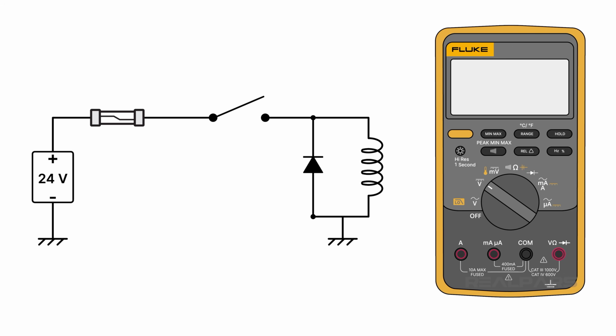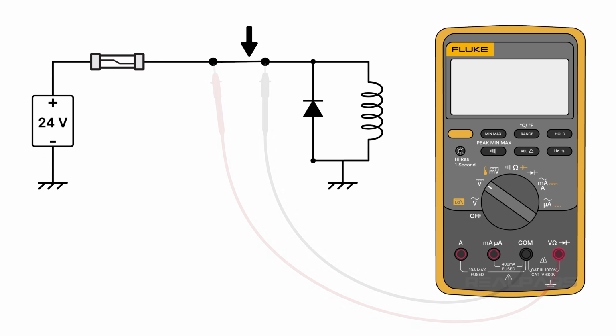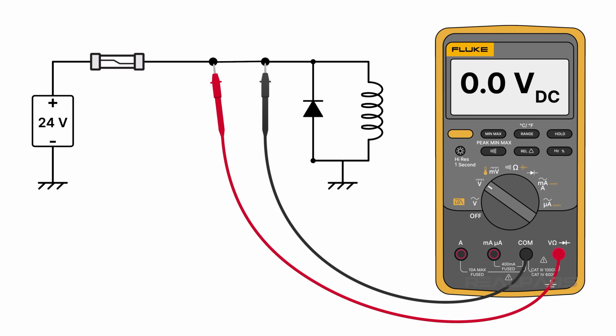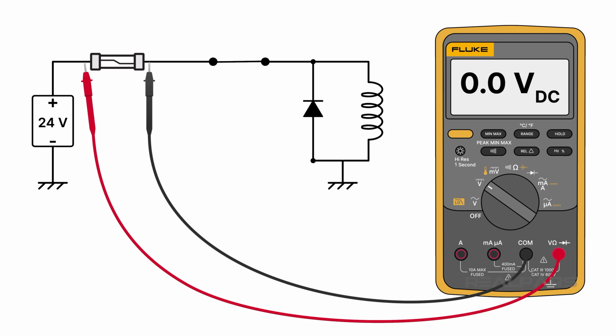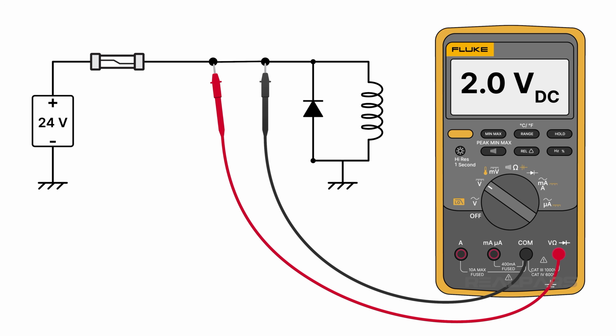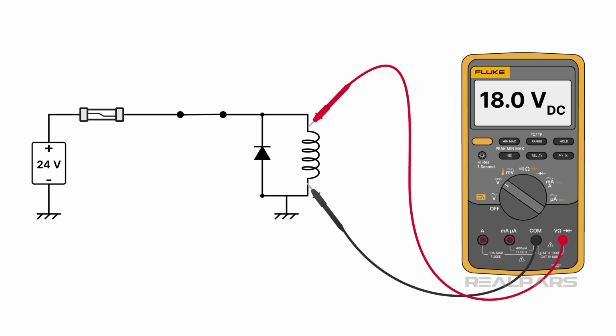Principle 2. Unexpected voltage drop indicates high resistance. Let's break that down. You shouldn't measure any significant voltage across a closed switch or a good fuse. Why? Because each has a normal resistance near 0 ohms. If you do measure voltage across a closed switch, it has an unwanted increase in resistance. If you have a decrease in voltage across a solenoid or any other load, it means there is a voltage drop increase across something else.